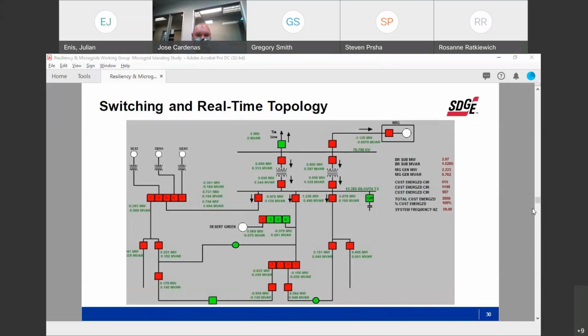We also have phasor measurement unit data, PMU data, being fed back to us as well, giving us the power flow across any one of those switches in the field. This is being sampled at 30 samples per second. So this is a high rate of communication going from field devices to substation devices to a microgrid. It requires a reliable, fast communication network. We've had to add a microwave power link to add that fast communication and reliability to our system.